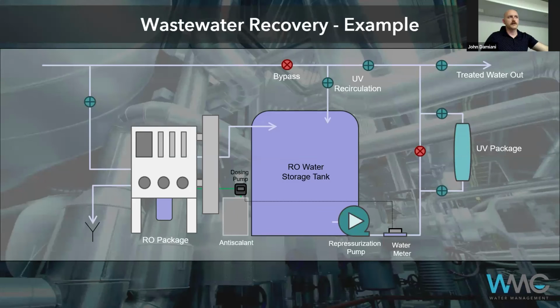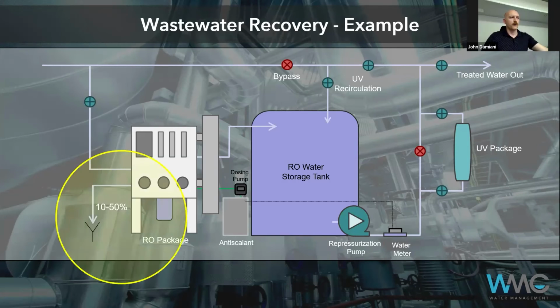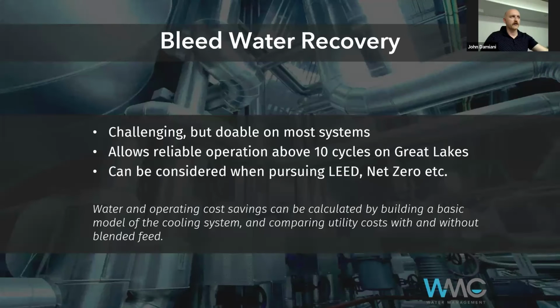This is an example of an RO system. Some facilities might have a small lab or other process producing RO water, and ROs reject water—anywhere from 10 to 50% of the water going in ends up back down the drain, depending on the quality of the RO, its size, flow rates, and the water quality needed out of it. Even if it's 25% of all the water going to that RO, that can add up to a lot. So instead of sending it to drain, in a lot of cases it can be sent directly to the cooling tower for a pretty big saving.